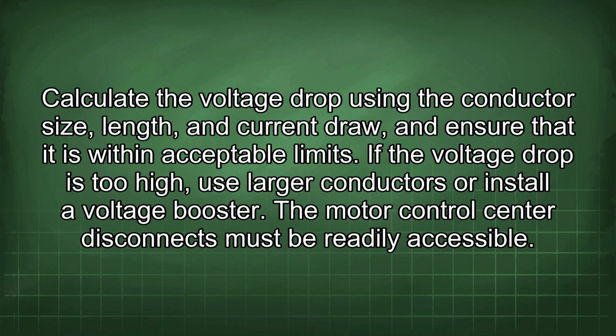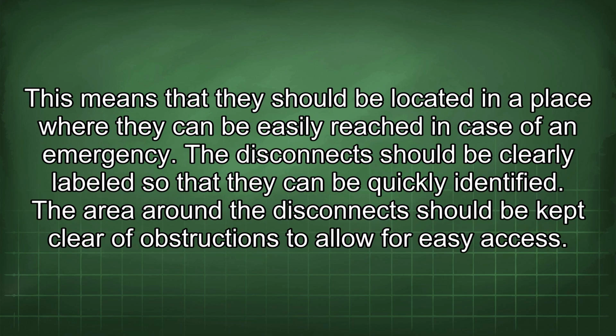The motor control center disconnects must be readily accessible. This means that they should be located in a place where they can be easily reached in case of an emergency. The disconnect should be clearly labeled so that they can be quickly identified. The area around the disconnect should be kept clear of obstructions to allow for easy access.